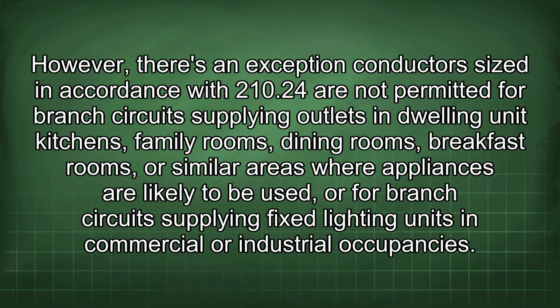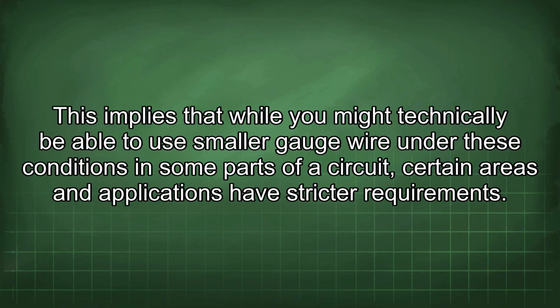However, there's an exception: conductors sized in accordance with 210.24 are not permitted for branch circuits supplying outlets in dwelling unit kitchens, family rooms, dining rooms, breakfast rooms, or similar areas where appliances are likely to be used, or for branch circuits supplying fixed lighting units in commercial or industrial occupancies. This implies that while you might technically be able to use smaller gauge wire under these conditions in some parts of a circuit, certain areas and applications have stricter requirements.